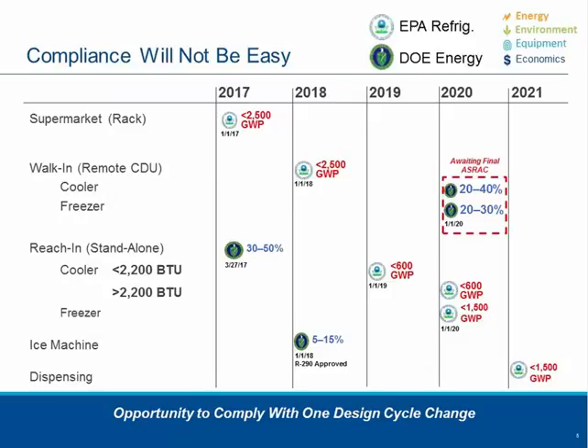The biggest challenge we have facing as an industry, that end users and others need to be aware of, is that equipment manufacturers are really pressed to meet these regulations that you see on this page in a relatively short period of time. We've had regulations in the past from the Department of Energy when it comes to commercial refrigeration equipment. We've had them in 2010 and in 2012. However, I would like to point out that those were almost a way for the Department of Energy, which, by the way, is using the consulting arm of Navigant, to really understand what's out there in the installed base. Now the levels at which the improvements are required are significant and posing challenges to equipment manufacturers.